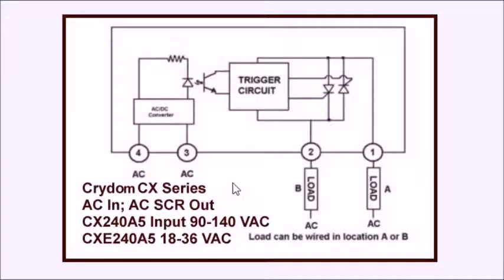This is an internal block diagram of the Crydom CX series with AC input. It has an AC to DC converter and your usual LED photo emitter, but this uses a photo transistor circuit that trips on a trigger circuit that trips on two back-to-back SCRs. As this shows, the AC load can be connected either in side A or side B. It doesn't matter.